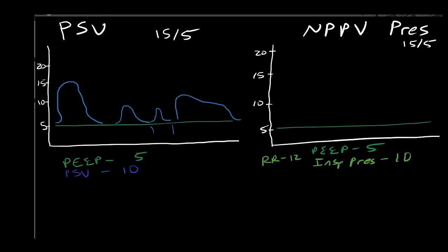Now, in NPPV mode, we have a minimum rate. As long as they're breathing faster than the rate of 12, then they get to choose their own respiratory rate. This is a conscious person, and they get to set the rate to whatever they want. Our inspiratory pressure is 10, our PEEP is 5, so we have that minimum, and then it's going to be additive, so it'll be 15. Whenever they breathe in, they are going to get 15. The key difference is if they only want a short little breath, and they try for a short little breath, the NPPV demands that 15 be reached, and so it's going to add and give them the full 15.